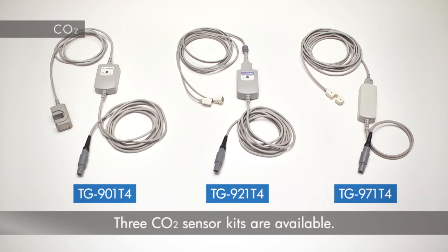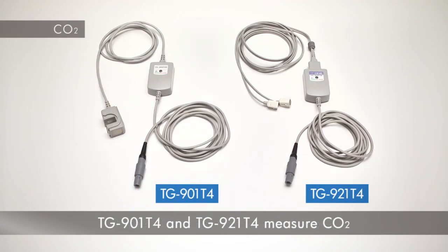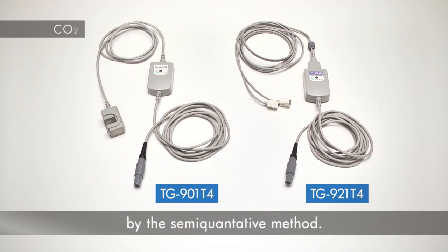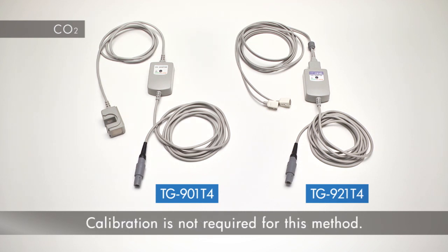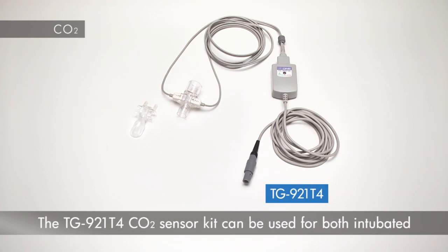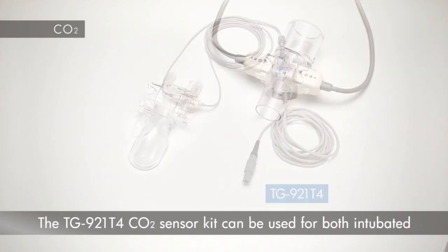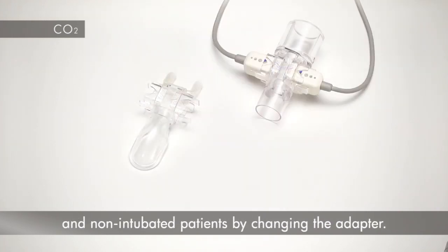Three CO2 sensor kits are available. TG901T4 and TG921T4 measure CO2 by the semi-quantitative method. Measurements are based on the assumption of no CO2 gas in the inspiration. Calibration is not required for this method. The TG921T4 CO2 sensor kit can be used for both intubated and non-intubated patients by changing the adapter.